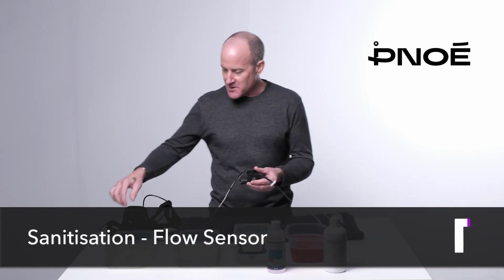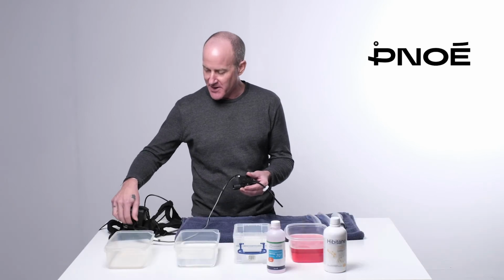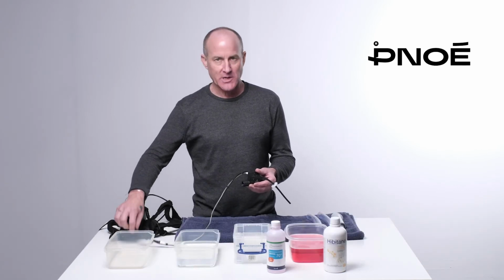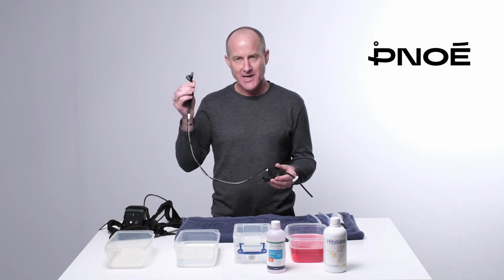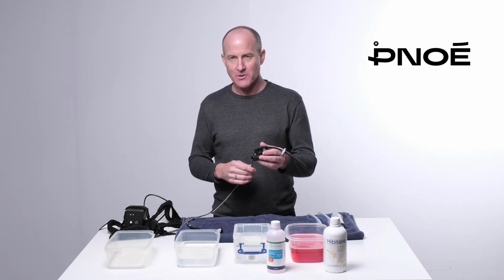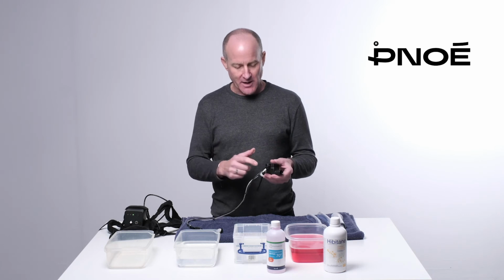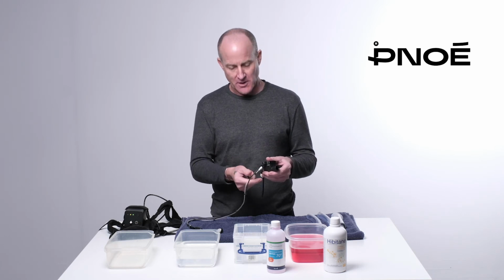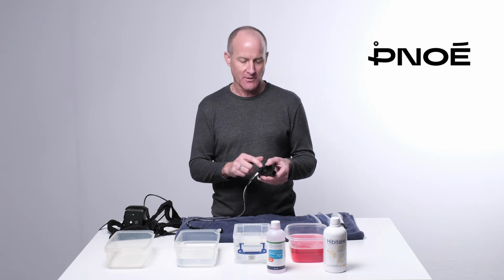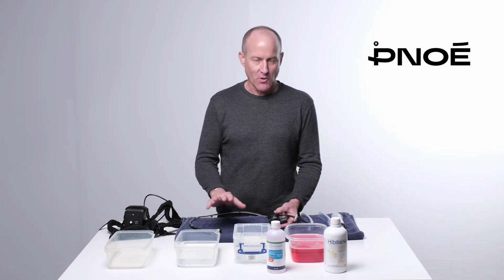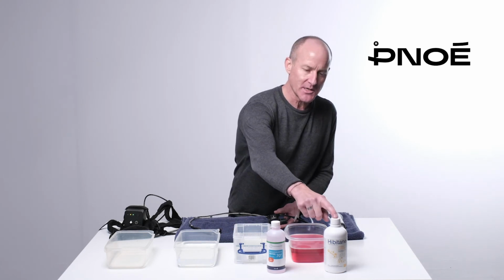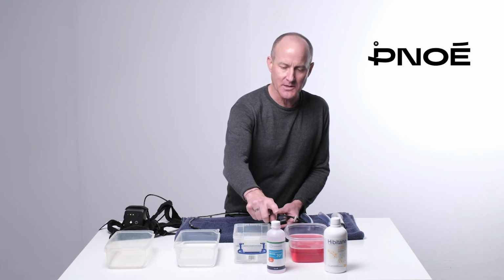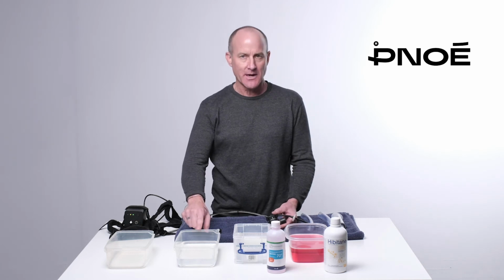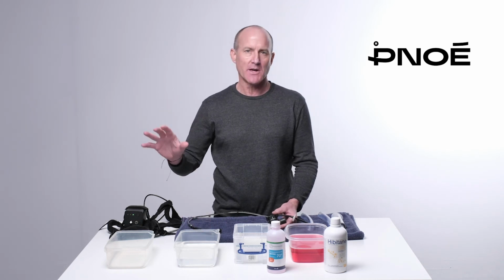It's imperative that the flow sensor is detached from the PNOE device. So use the quick releases, and of course you must protect the charger cable and the flow sensor cable, and be aware of not putting pressure through the wire insertion into the flow sensor itself. The cleaning process is four parts. The first is a clean with Hibiclens or HibiTane, then a 70% alcohol solution, followed by cleaning with deionized water, followed by a drying station.